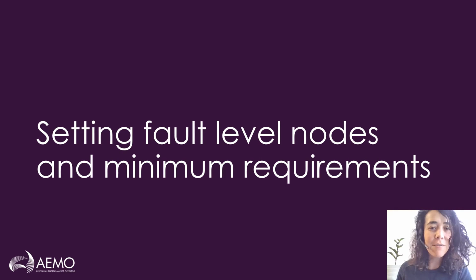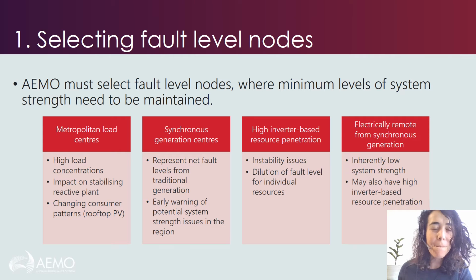Now to how we set the fault level nodes and the minimum requirements. First of all, we take a look across the network and we see where would be a good point to measure how system strength is going. We have decided that as AEMO, we think it's appropriate to look at a variety of different points with different properties when we're looking at system strength.